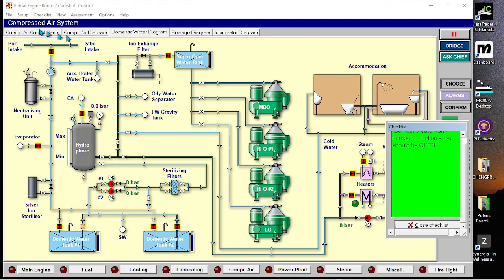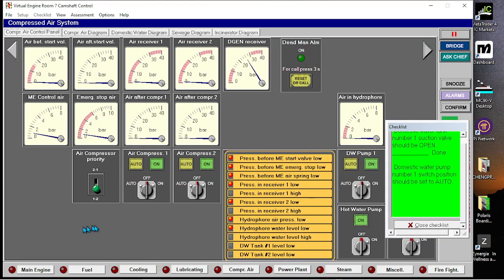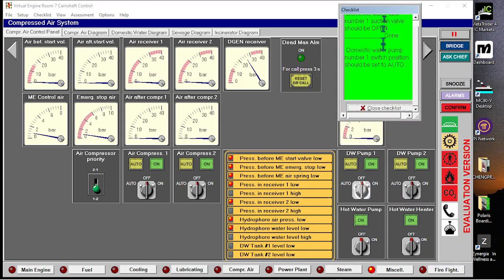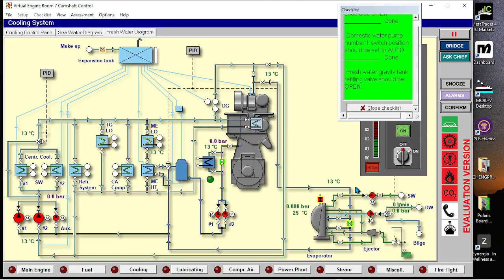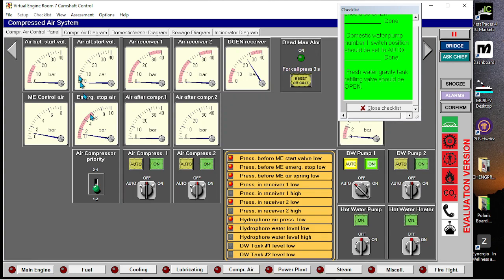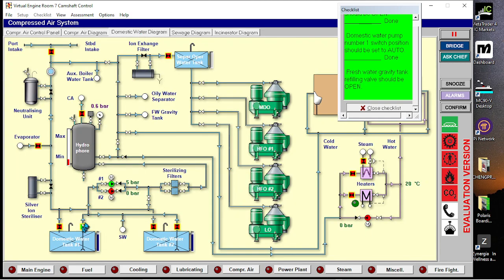So this is now the domestic water diagram. For domestic water tank number 1, we will open this valve. Domestic water pump number 1 switch position should be set to auto. So this is the domestic water pump, and we're going to switch this into auto. Freshwater gravity tank refilling valve should be open. So we will go back to this page. We will check first the domestic water diagram. From here it goes here, filling our hydrophore tank, and it goes into this line going to the freshwater gravity tank.